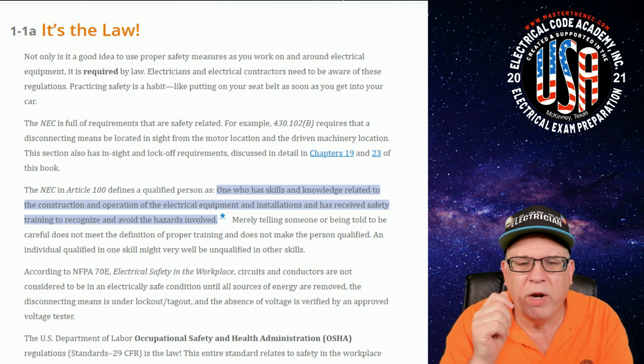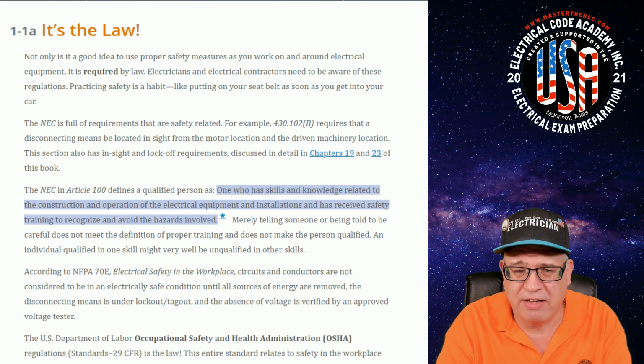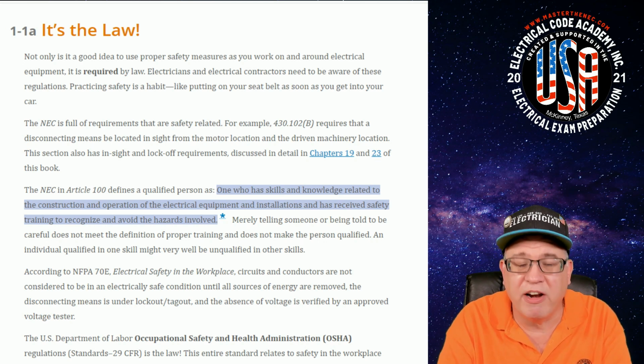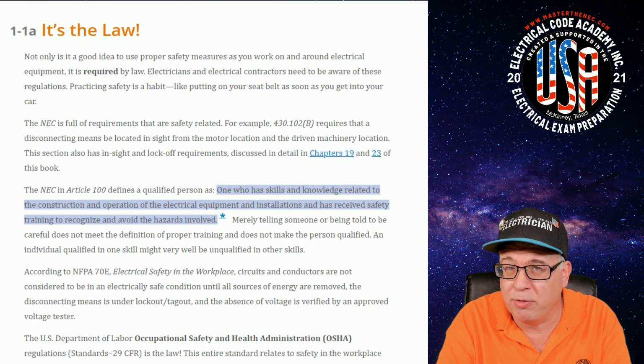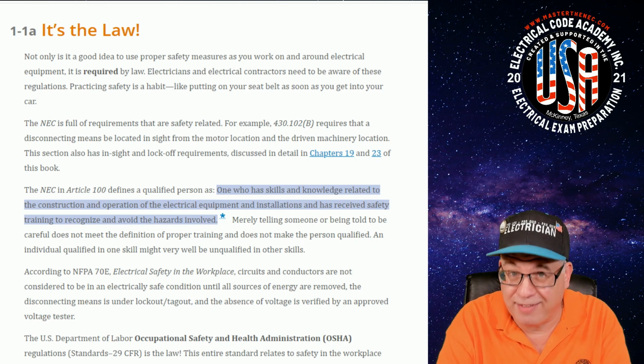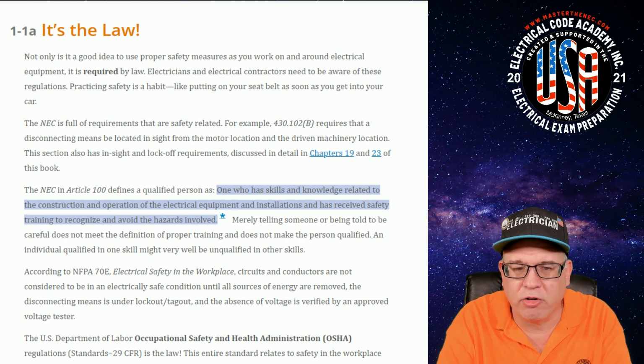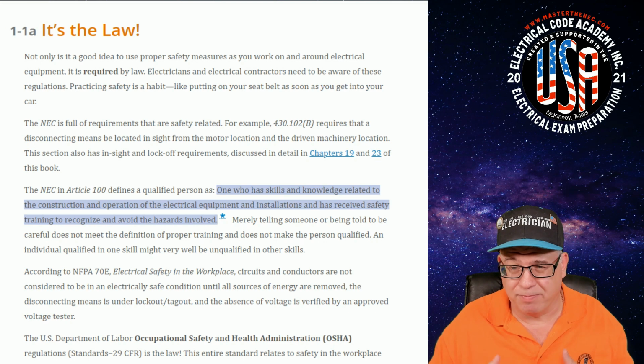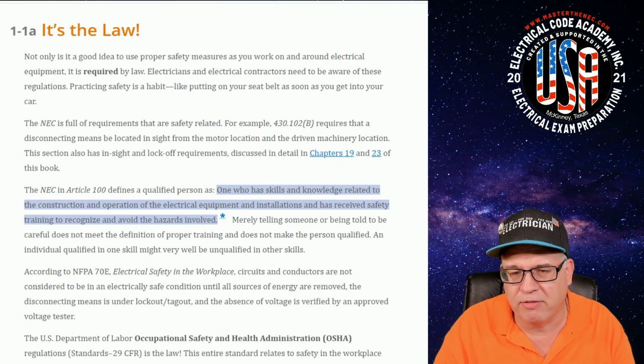Now, here's what NFPA 70E actually says: circuits and conductors are not considered to be in an electrically safe condition until all sources of energy are removed. It's exactly what it says—de-energize it. It says the disconnecting means is under lockout and tagout, and the absence of voltage is verified by an approved voltage tester. All of this is what we talked about—making sure your voltage tester works, and making sure you have a procedure in place to do that.